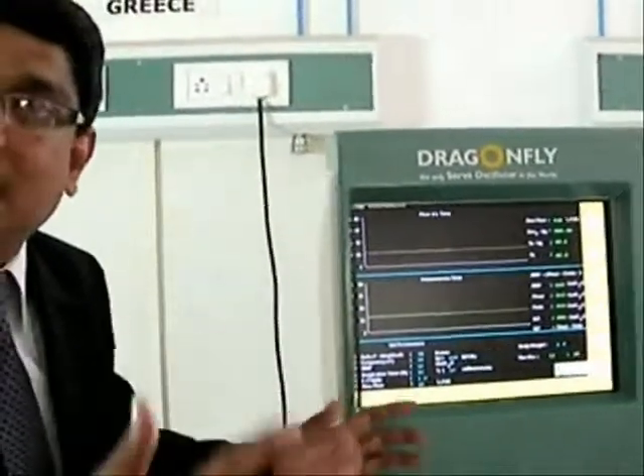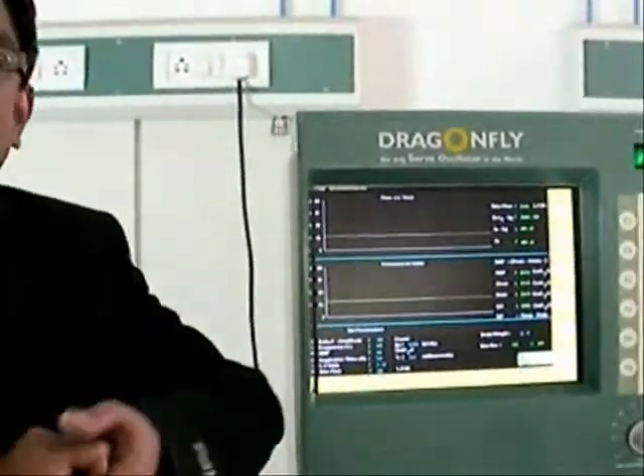Simultaneously, if you increase or reduce the frequency, again there is a change in the pressure. For example, if I reduce the frequency from say 10 Hertz to 8 Hertz, the time allocated for inspiration increases. So obviously more volume goes in, so the pressure increases. To overcome this problem, we have made a servo control mechanism in our device. So the pressure and the flow both go hand in hand. They are not independent as in the Sensormedics 3100A.